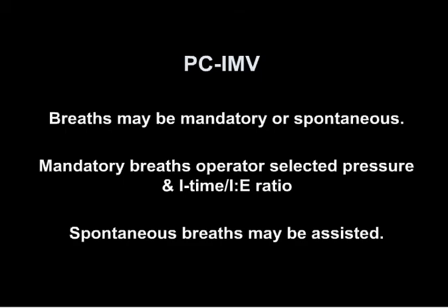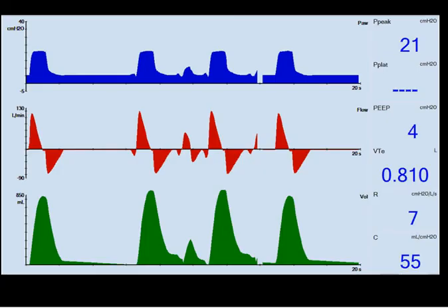Pressure control IMV: breaths may be mandatory or spontaneous. Mandatory breaths are operator-selected pressure, with a constant I-time and IE ratio. Spontaneous breaths may be assisted. In the waveforms, we see fixed mandatory breaths at a fixed pressure for a fixed amount of time. The flow waveform shows flow distortions, and the pressure waveform reveals spontaneous breaths in between mandatory breaths. The spontaneous breaths are not for a fixed amount of time and look totally different from the mandatory breaths. This patient is on pressure control IMV with approximately 5 centimeters of water pressure support to augment spontaneous breathing.